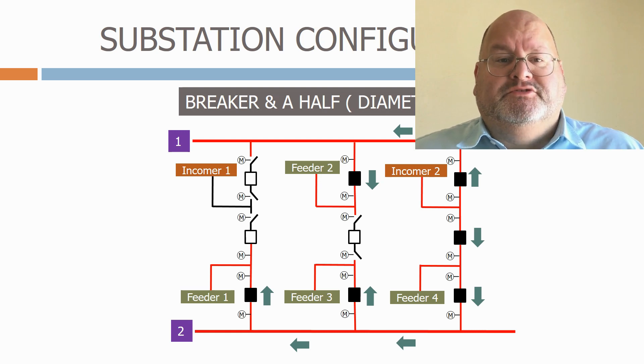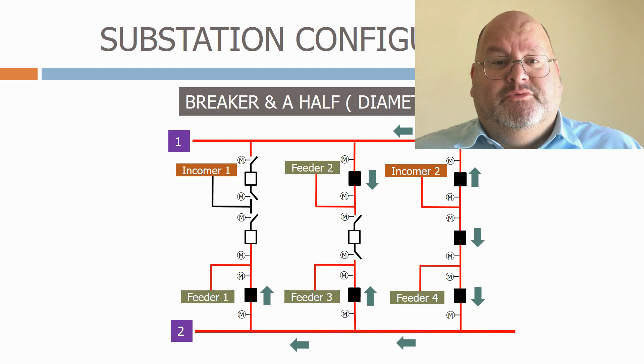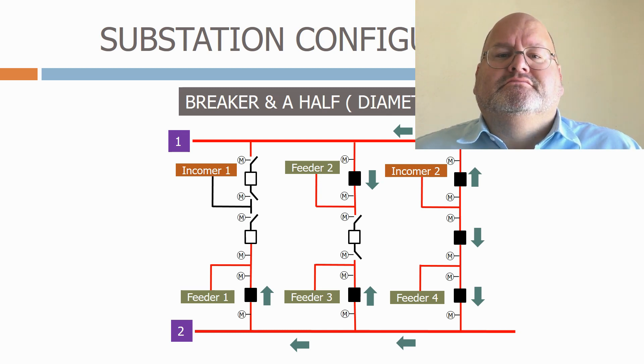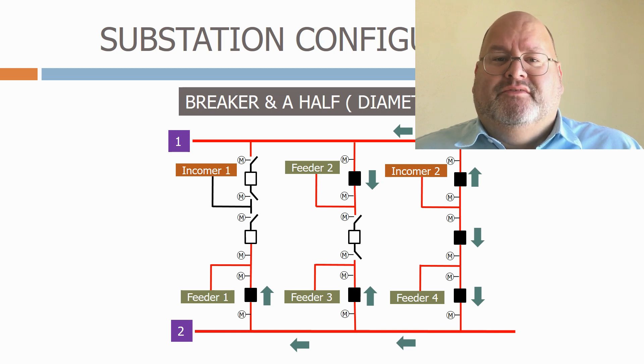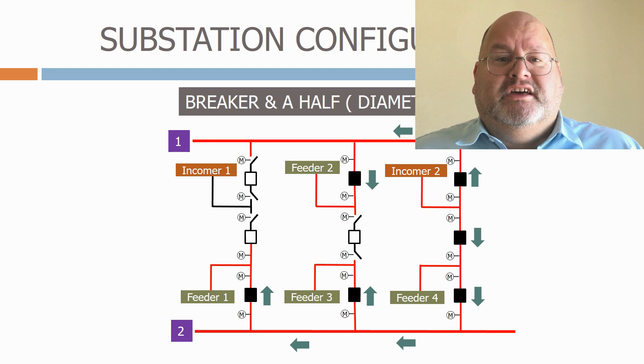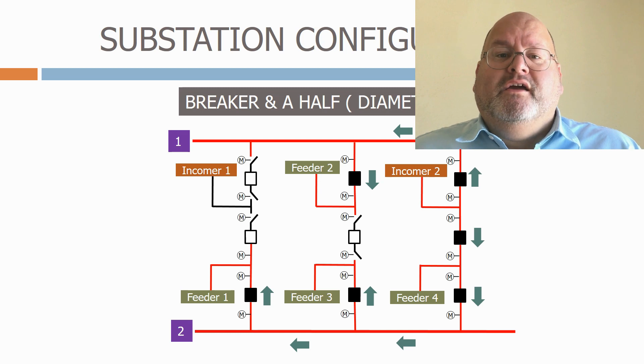The breaker-and-a-half arrangement is popular around the world as it gives a cost-efficient way of providing a very flexible design which is easy to expand should system demands increase. The number of bays that can be tied together is virtually unlimited — I have worked on high voltage transmission substations that have had over 25 diameter bays. The layout of a diameter substation also takes up less physical space compared with an equivalent double bus bar substation, which can save substantial amounts of money on land purchase.